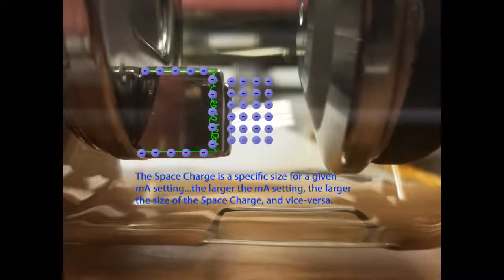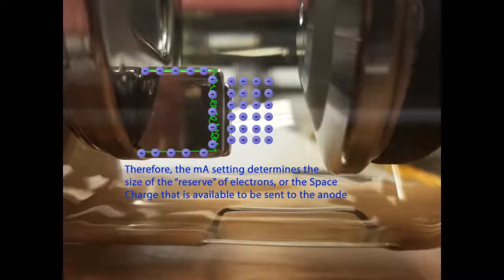The space charge is a specific size for a given mA setting. The larger the mA setting, the larger the size of the space charge, and vice versa. Therefore, the mA setting determines the size of the reserve of electrons, or the space charge that is available to be sent to the anode.